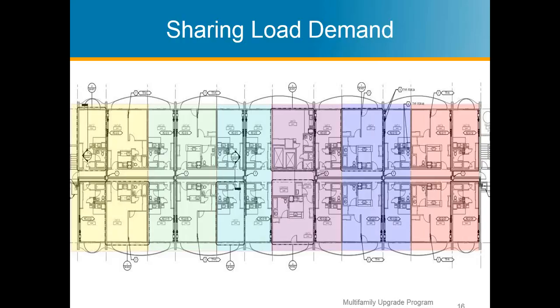I know that most of the time people do just an average square foot per ton type situation, and that way is a way of the past. It's not something that is going to stand. I've had a lot of enforcement agencies ask for mechanical HVAC load summary reports and things of that nature, and you do get penalized in the Title 24 reports when you oversize equipment. So these smaller units are awesome when you can get down to the half ton, and it has that range.